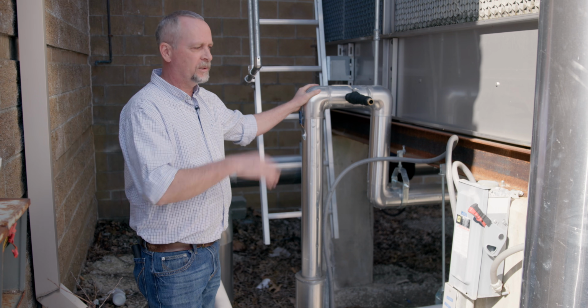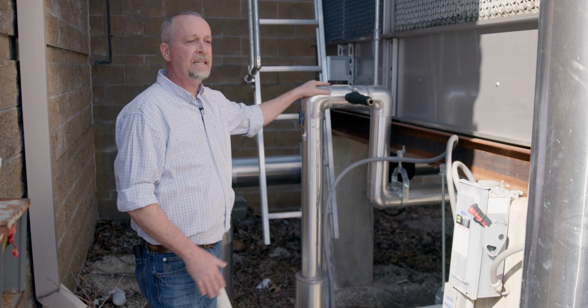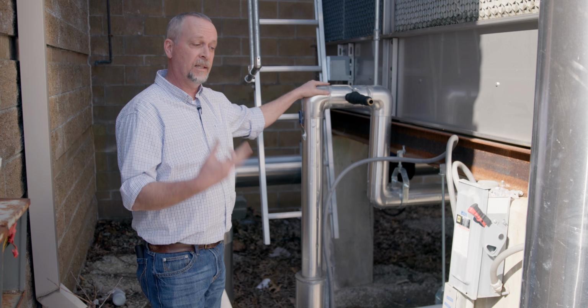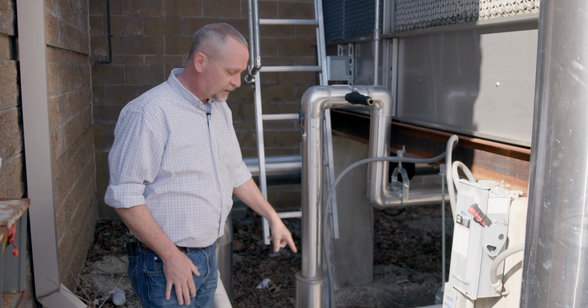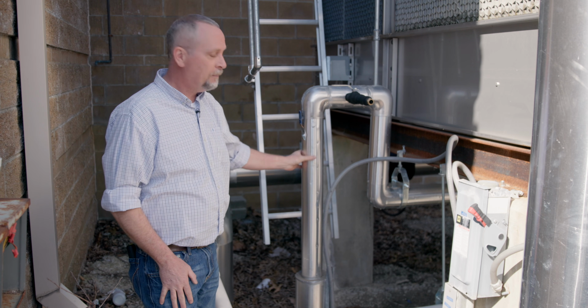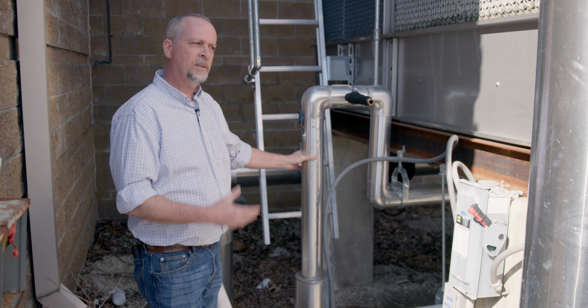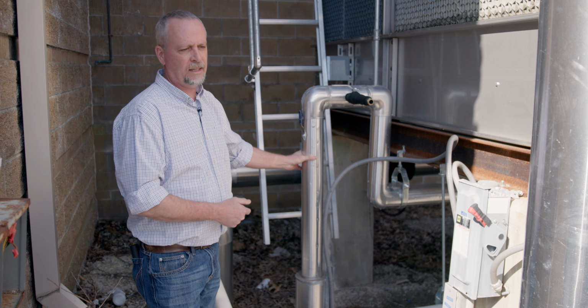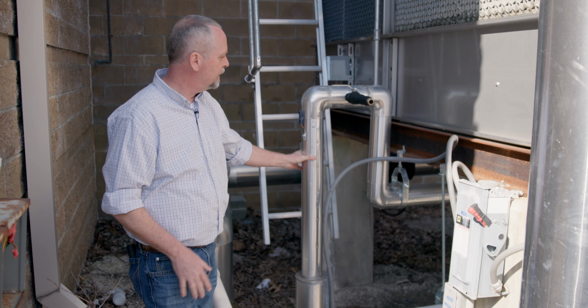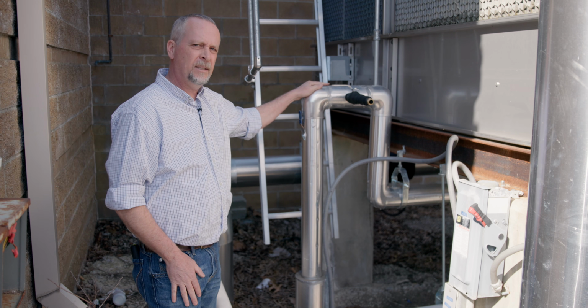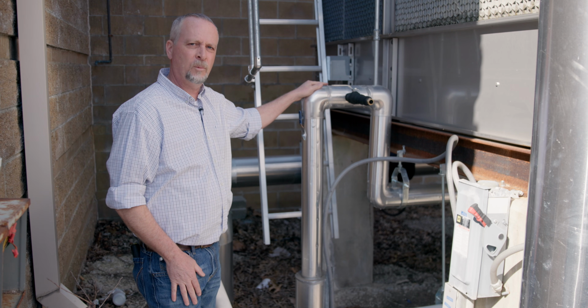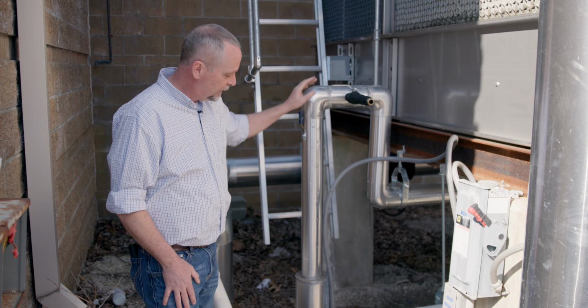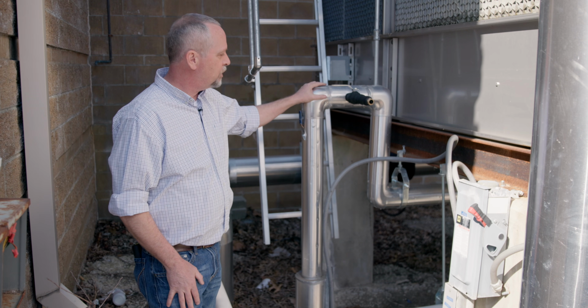There's a valve that opens and closes, so when the water stops moving, it's gonna freeze a whole lot quicker. And when we get in the wintertime, this item's missed all the time. It may be there, but it doesn't work, you know? So another thing, you really wanna make sure you check that heat trace when you're doing your preventative maintenance, because if you're doing the maintenance and then it freezes and busts in the winter, guess who's gonna be paying for that? So always check that heat trace, make sure it works.